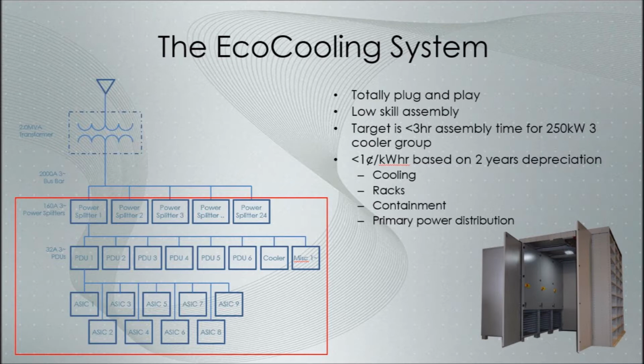That's what we're going to see, that's the way we're going to match the rest of the world in rapid deployment of these new technologies. And maybe we can get our total cost of ownership for that part of the infrastructure down to less than 1 cent per kilowatt hour. Remember that value of 5, 6, 7 cents per kilowatt hour? We've got to have this infrastructure to house this equipment. Now, if we're using less than 1 cent on the main part of the capital, we've just got to find a building, find a transformer, get some comms into it, then we stand a chance of competing. And you're not going to do it with any of the conventional solutions.